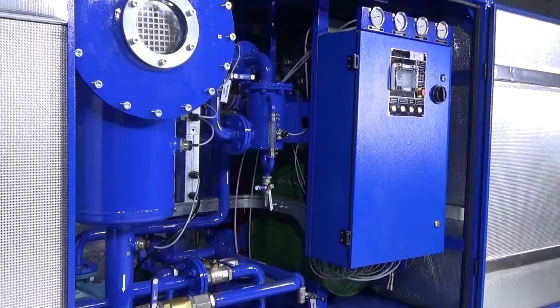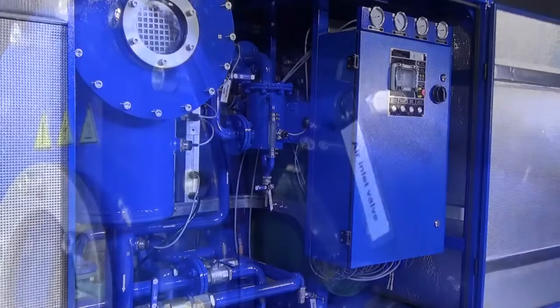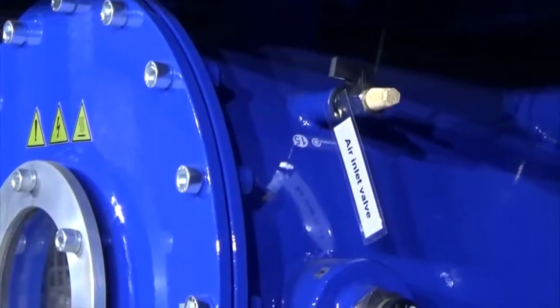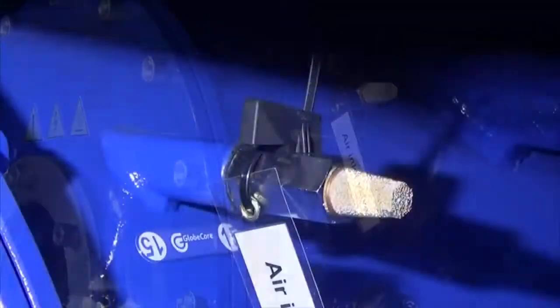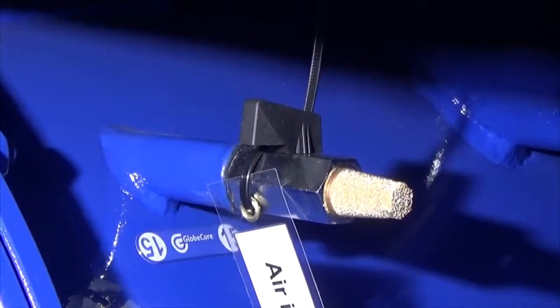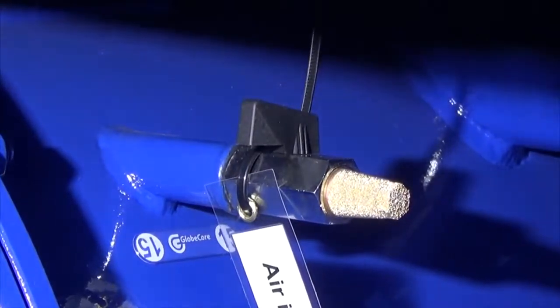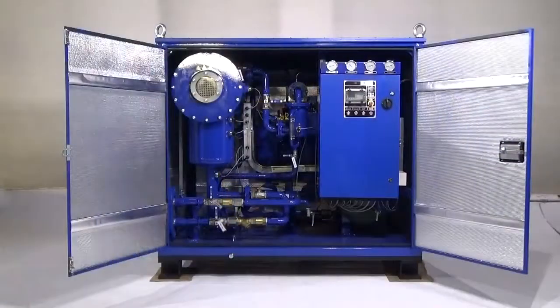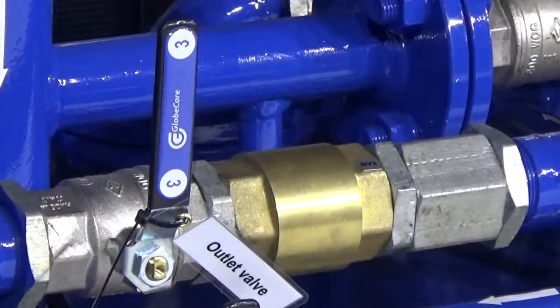With every cycle, foaming will diminish and the drying process will increase its efficiency. To reduce foaming and the frequency of the air inlet valve opening, slightly open valve MV15, thus reducing vacuum in the chamber. This, however, will reduce the unit's processing rate. 8. Partially close valve MV3, raising the outlet pressure to 1.4 bars. The unit's processing rate will stabilize.